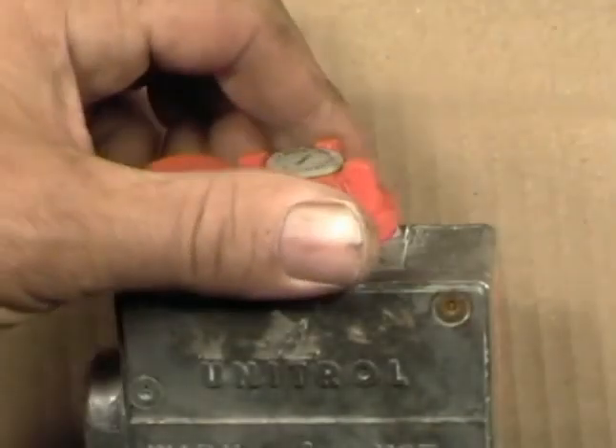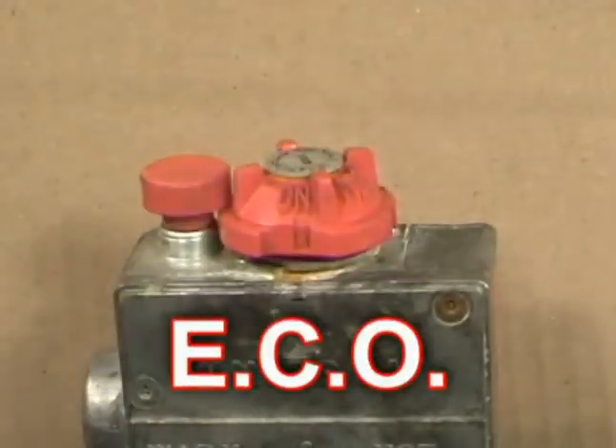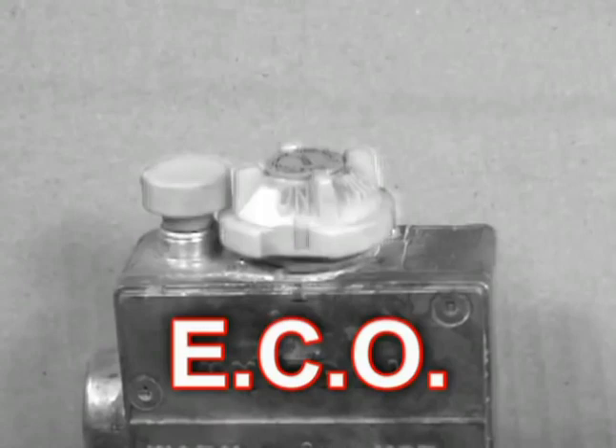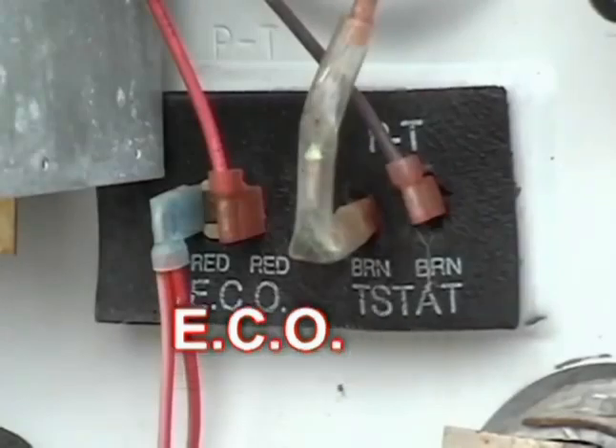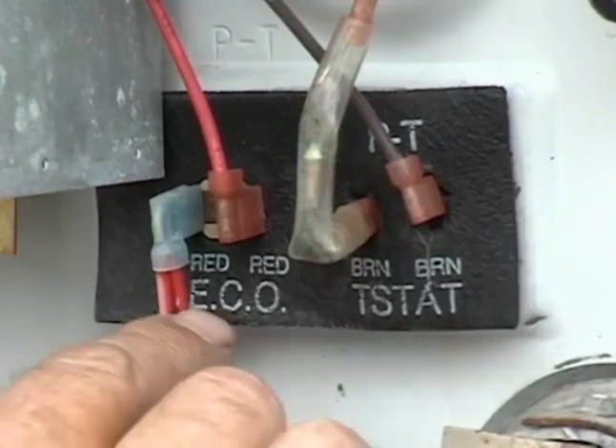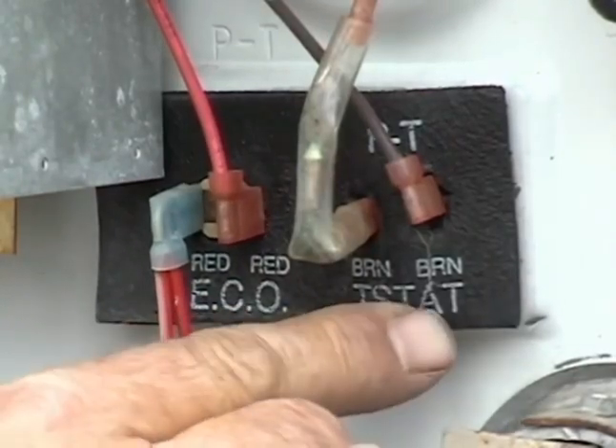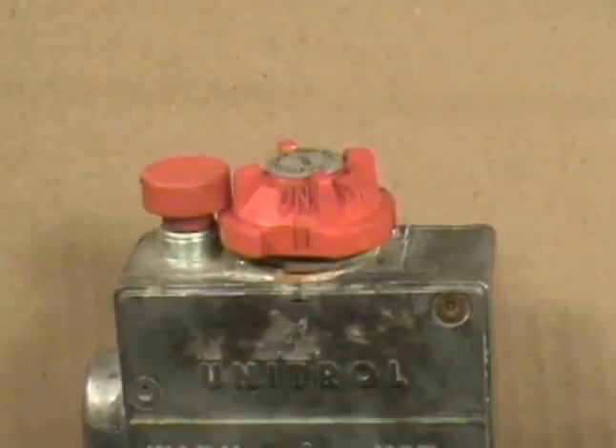This is very important. These controls have what is called an emergency cutout, or an ECO. It's a protection device designed to shut down the water heater if the temperature goes to an unsafe level. It's built into the control, and if problems arise, say no water in the tank or the thermostat goes bad, it shuts down and will not light again. The entire control has to be replaced.